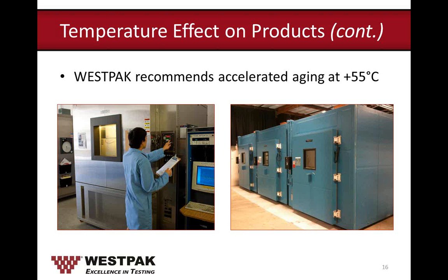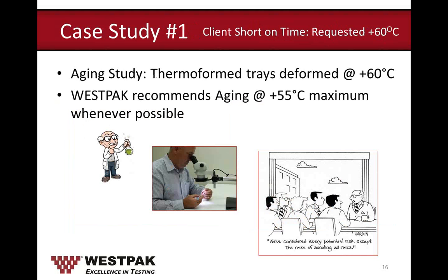Some customers are in a hurry and just want samples in the oven right away, accepting extra aging days. If you want accelerated aging conducted at a higher temperature — above 60°C — we do provide that service. However, I want to emphasize again: we don't recommend aging temperatures higher than 55°C with uncontrolled RH.